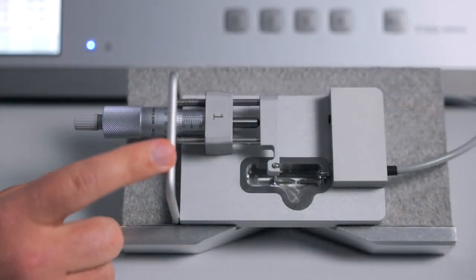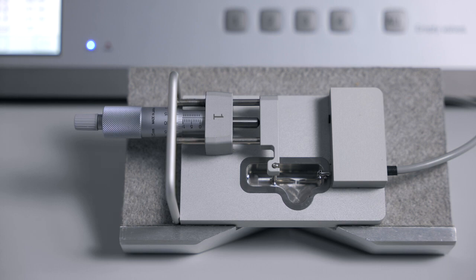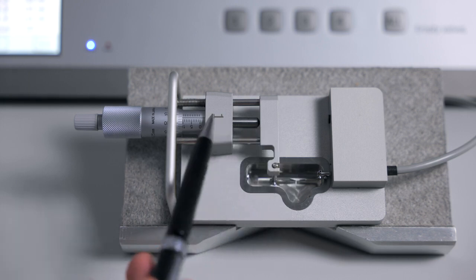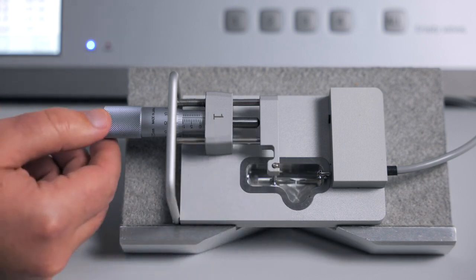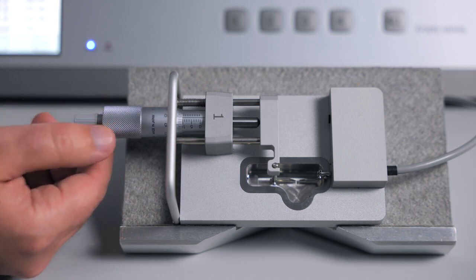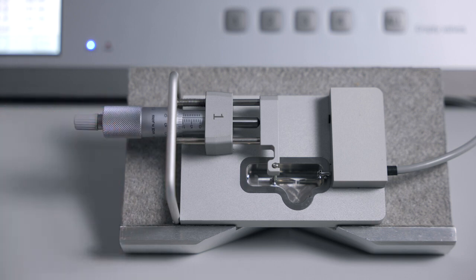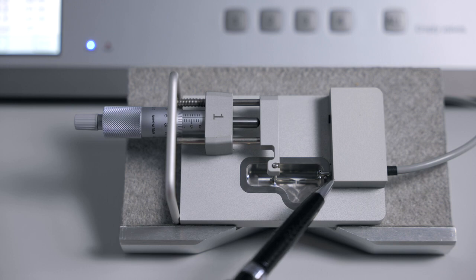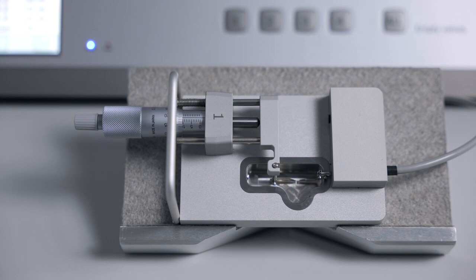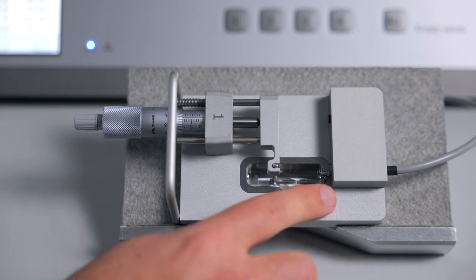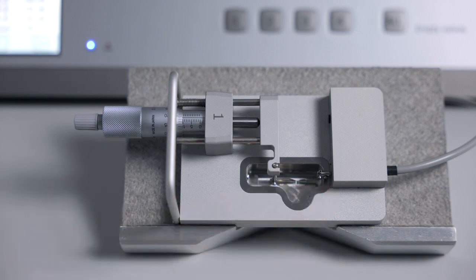The 820MO chambers can easily be removed from the interface and taken to a dissection microscope in order to facilitate tissue mounting. In the tissue chamber itself, there are 2 mounts, one connected to a micrometer that allows you to easily and accurately adjust the tissue length, while the second side is attached to a force transducer, which will give very accurate readings of the forces generated by your tissues. You must be careful with the force transducer, as this is the most sensitive part of the chamber.